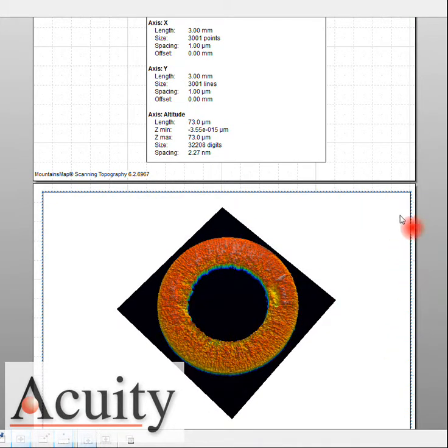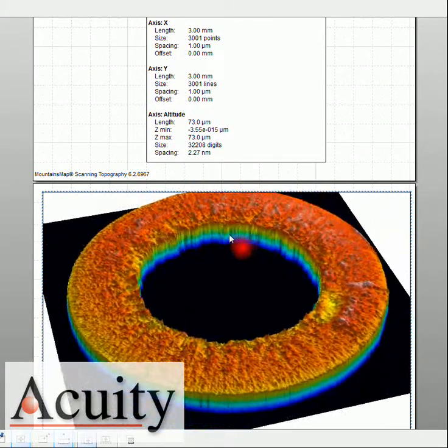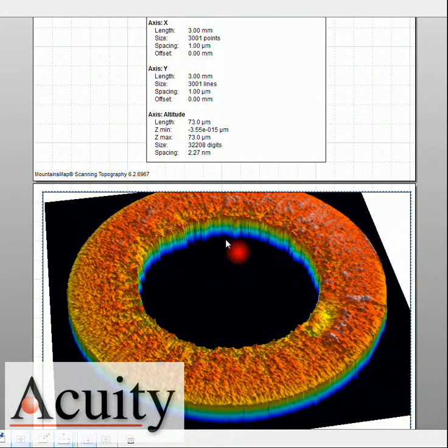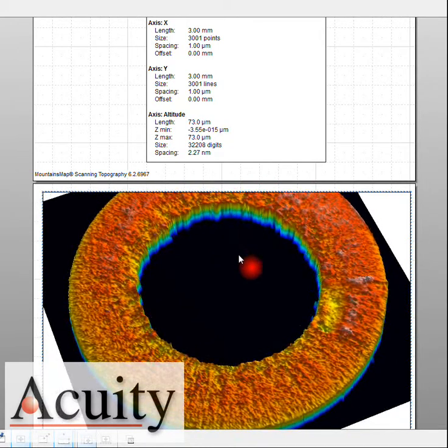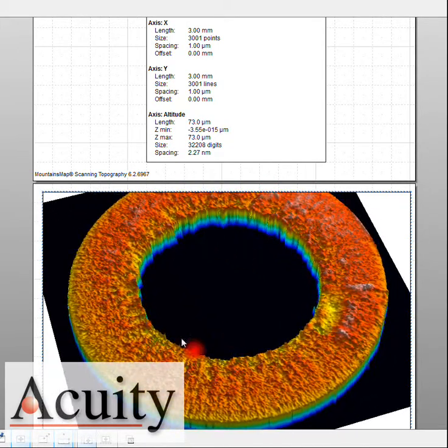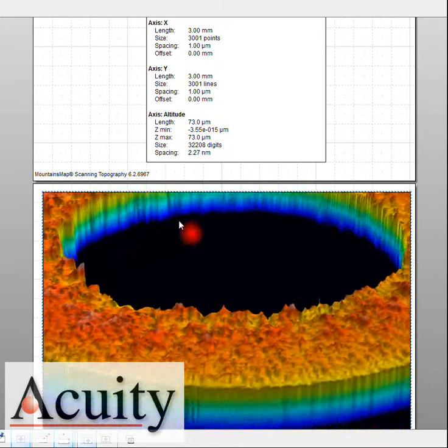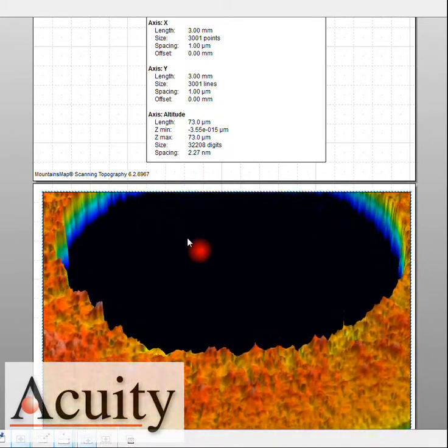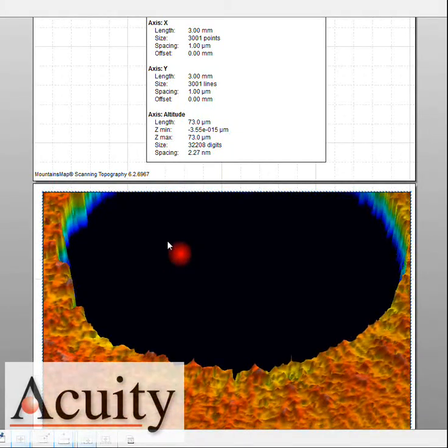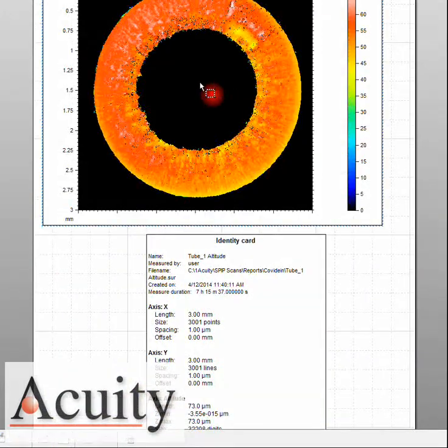And you can see pretty well that we're getting a very good representation to where we can see the surface roughness even on the part. And it is a little skewed, where the surface roughness is showing is not at the same dimension as the diameter. So we're actually accentuating the surface roughness of this part. So let's go back and see if we can measure that diameter.